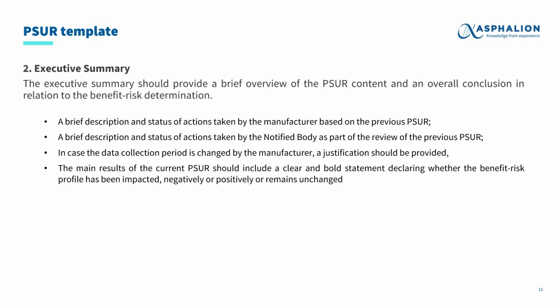Also, a brief description and status of actions taken by the notified body as part of the review of the previous PSURs. In case the data collection period is changed by the manufacturer, that means that, for example, for Class 2A medical devices, the PSUR should cover a period of 2 years. So if for any reason the manufacturer decided to change this collection period, the justification should be included here in the executive summary.